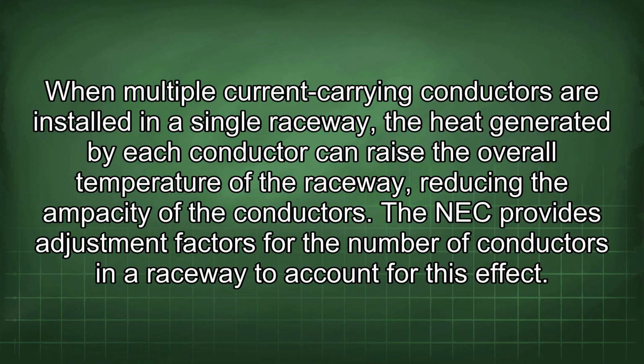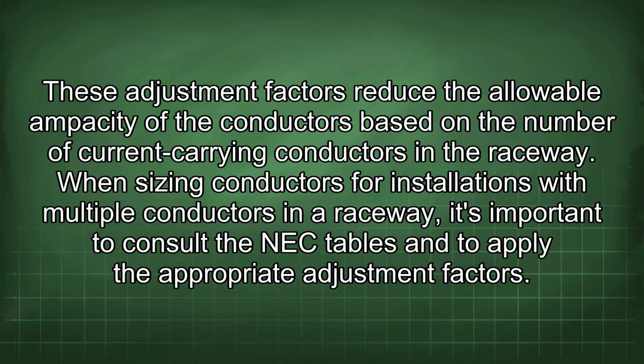The NEC provides adjustment factors for the number of conductors in a raceway to account for this effect. These adjustment factors reduce the allowable ampacity of the conductors based on the number of current-carrying conductors in the raceway. When sizing conductors for installations with multiple conductors in a raceway, it's important to consult the NEC tables and to apply the appropriate adjustment factors.